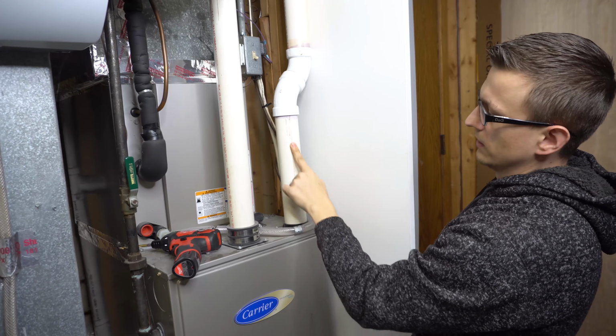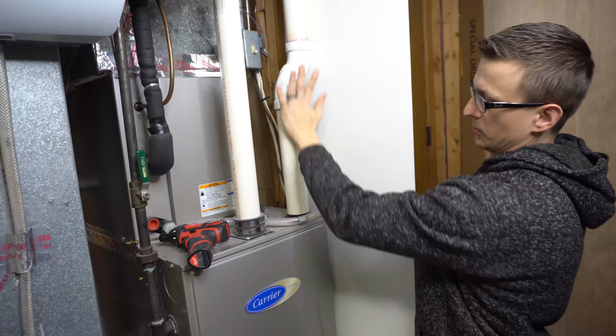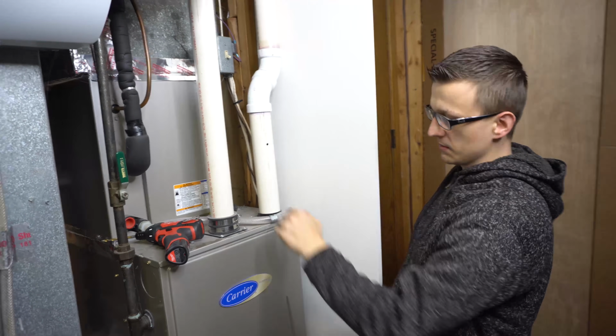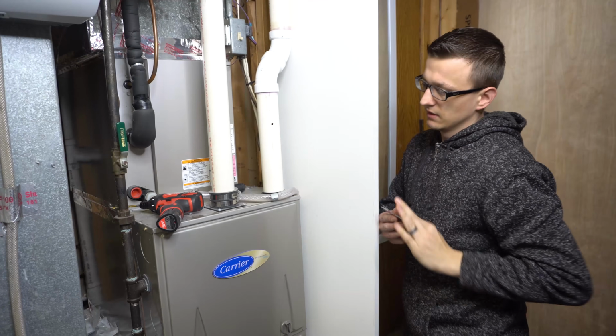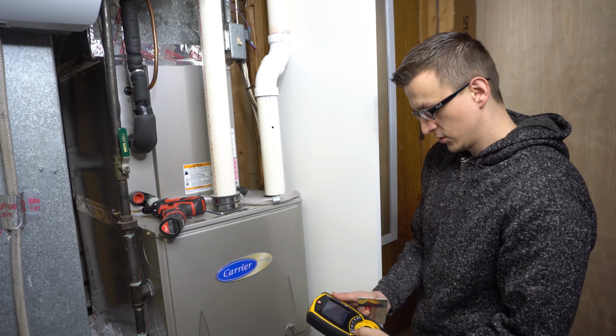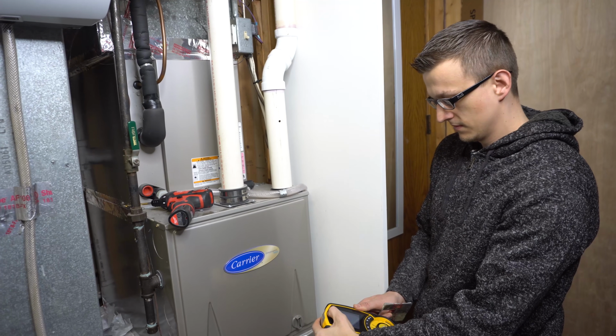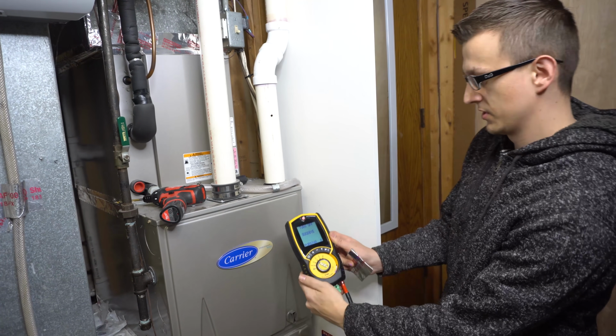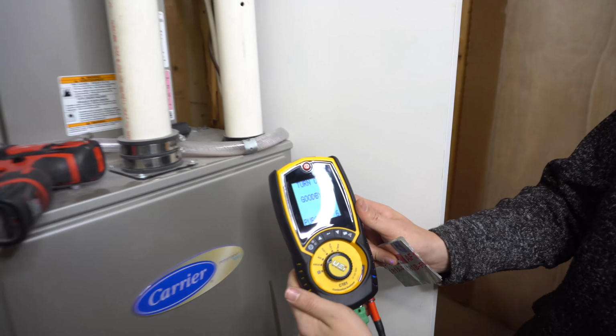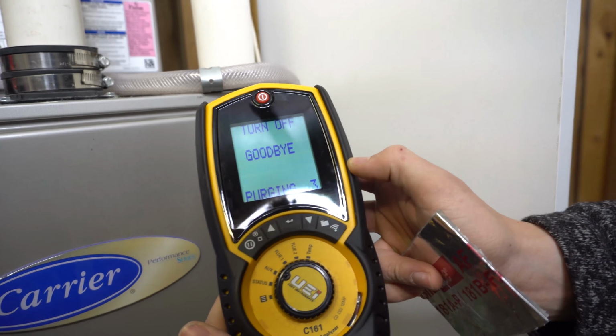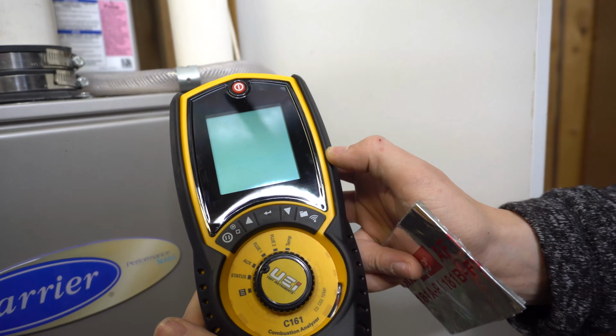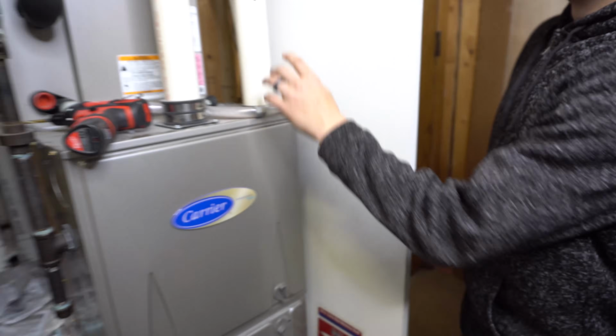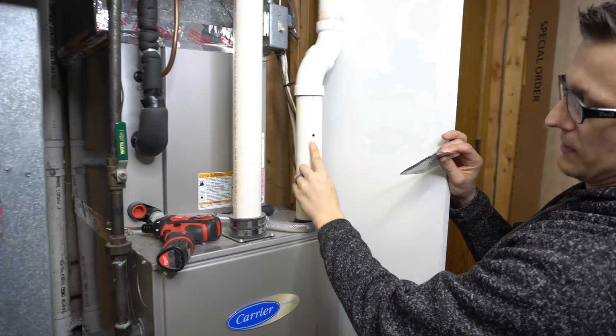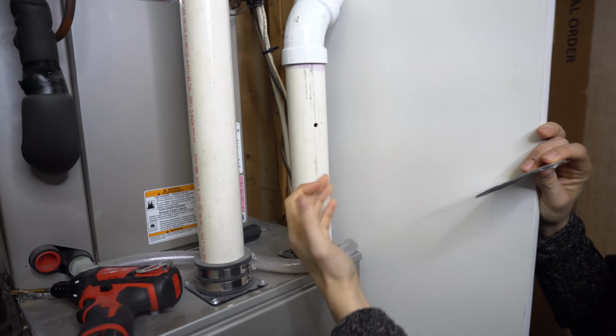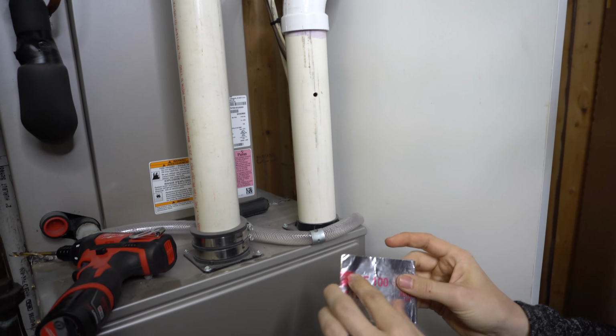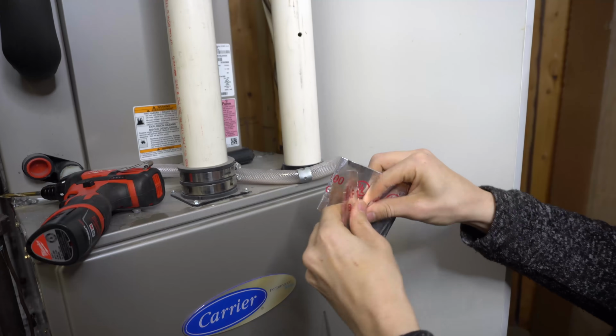And about the hole. Some people say that you're only supposed to put some silicone in there and then cover it up with tape, or just the silicone. Let me turn off my analyzer now so it's not buzzing in the background. See how it says turn off, goodbye, purging. It started at 10 seconds. Boom, turned off. Okay. So personally, I always tape these holes, even on high efficiency furnaces, even though it condenses and there's water. And I'll tell you in a little bit why.